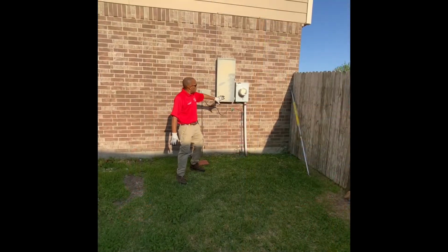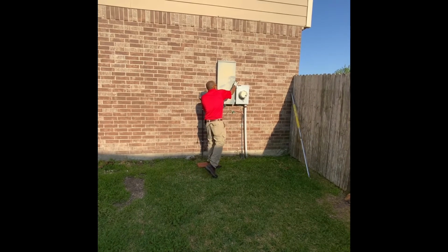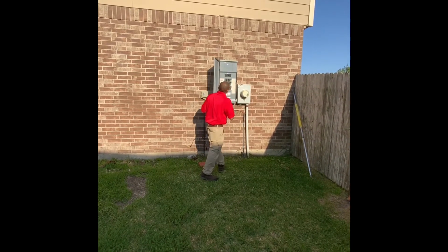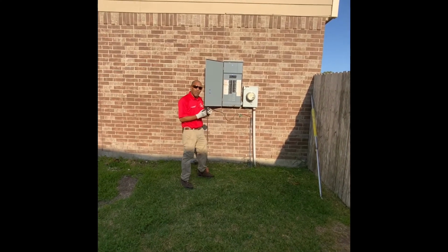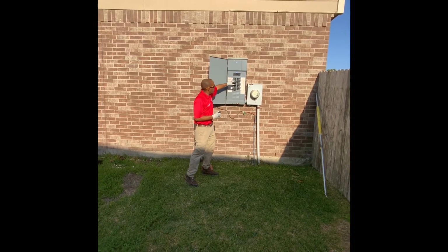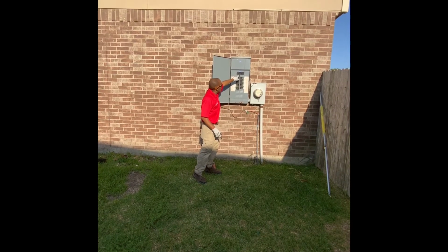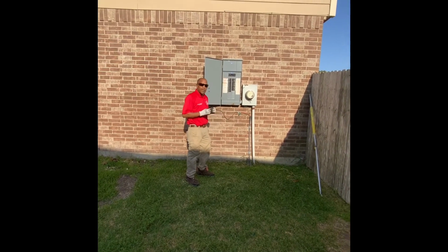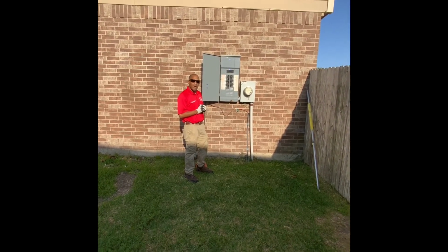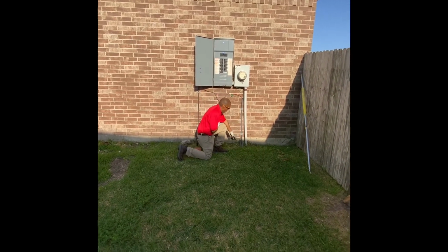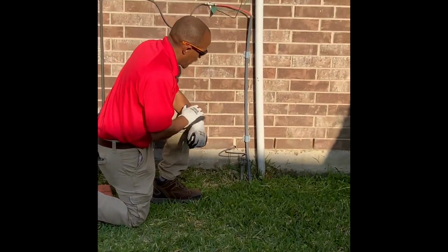We also inspect your electrical panel, your main panel. Some of the things that we check for: we look at your circuit breakers. We match the size of the wiring to the size of the circuit breakers, which is very important. We also look at your service amperage. In this case, this is 125 amps, and we need to make sure that that matches with the service entrance size that comes in as well. We also look at your grounding rod, to make sure your clamps are good and that your service entrance panel is grounded, and the condition of it.